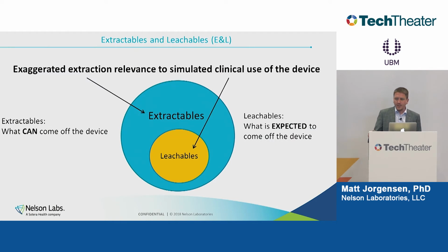Another great alternative to animal tests is extractable leachables. If you have any device that is permanently contacting the body, and many prolonged-contact devices should be in this group too, then you have all of these really burdensome biological endpoints to address: subacute, subchronic toxicity, genotoxicity, chronic toxicity, and carcinogenicity. Those are all endpoints that the FDA needs you to address.